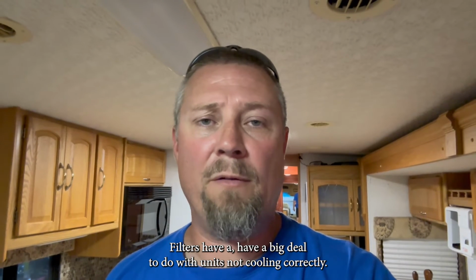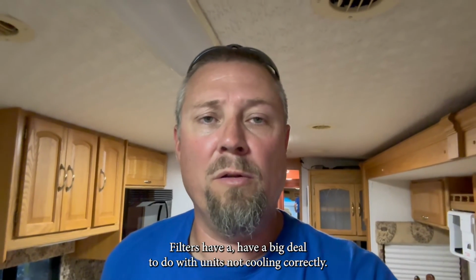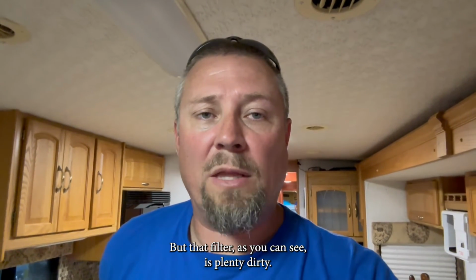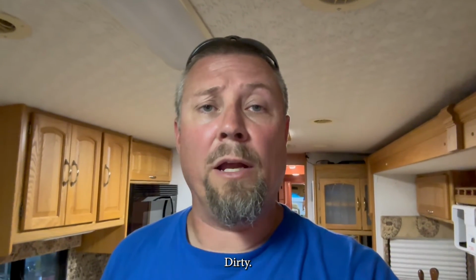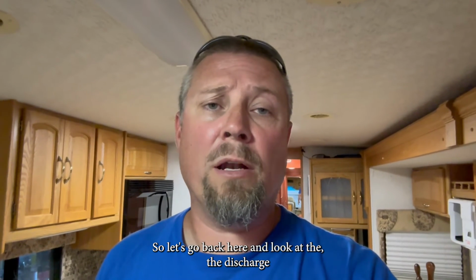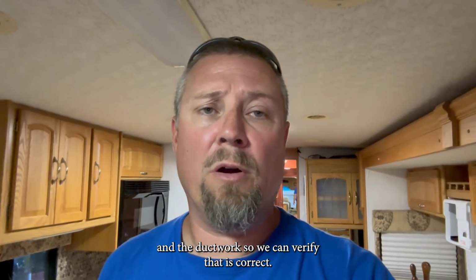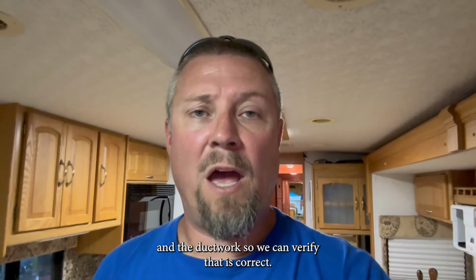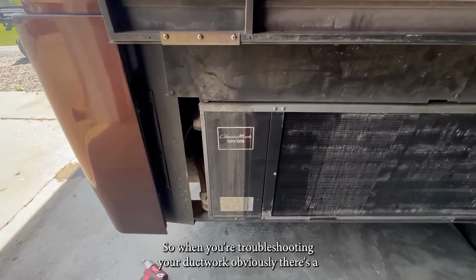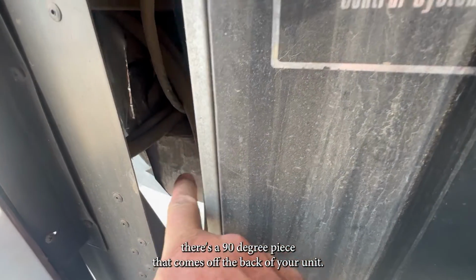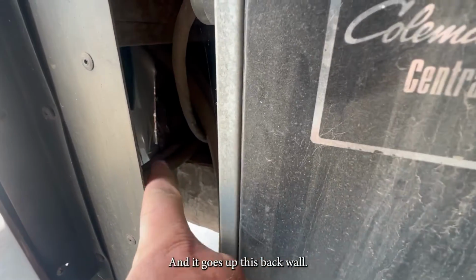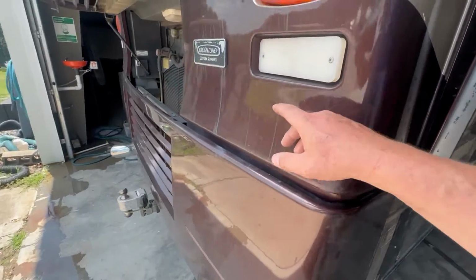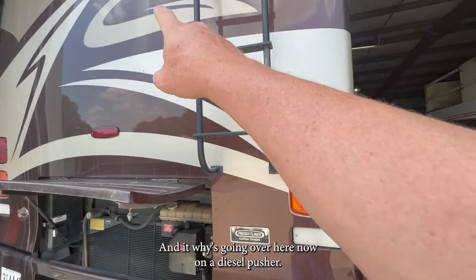Filters have a big deal to do with units not cooling correctly. But that filter, as you can see, is plenty dirty. So let's go back here and look at the discharge and the ductwork so we can verify that it's correct. When you're troubleshooting your ductwork, obviously there's a 90-degree piece that comes off the back of your unit and it goes up this back wall, and wires go over here.